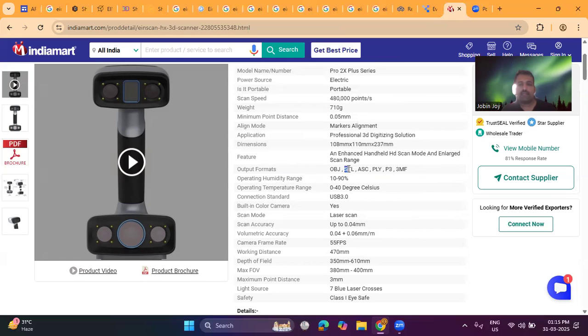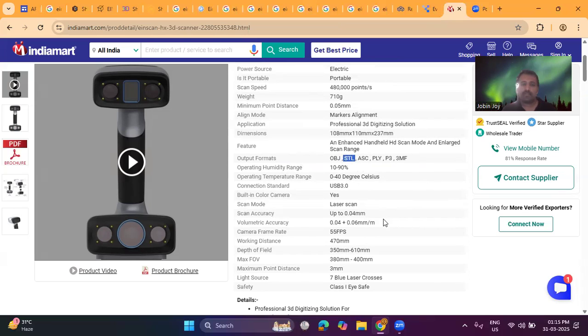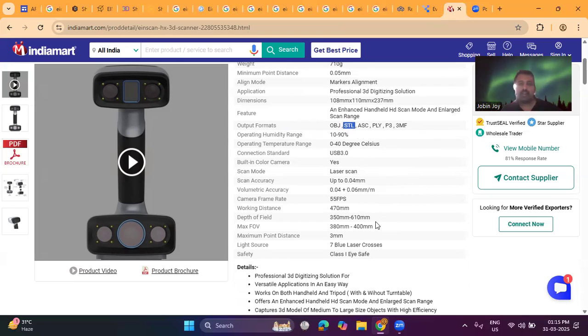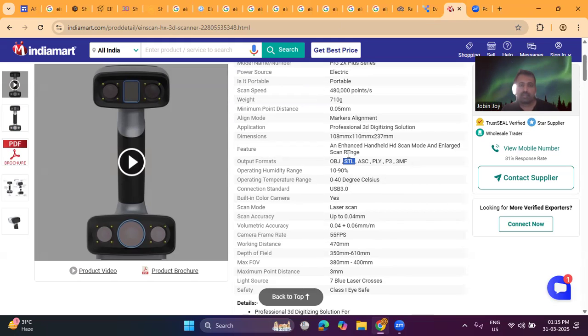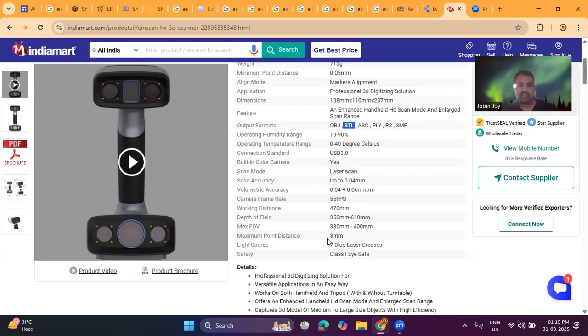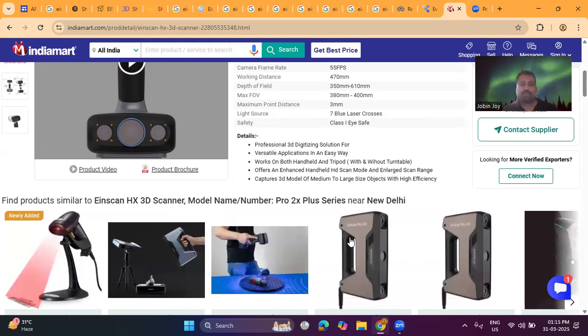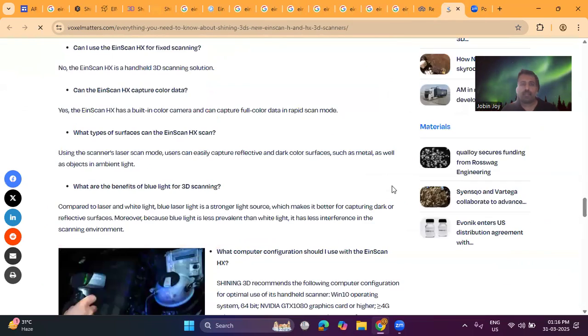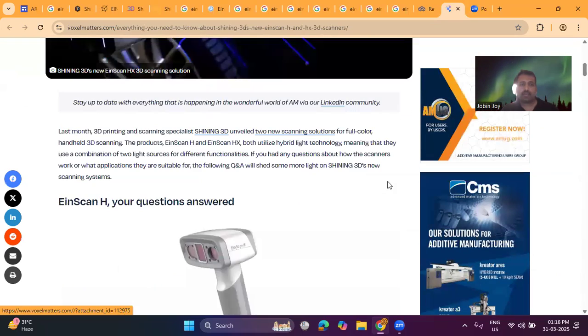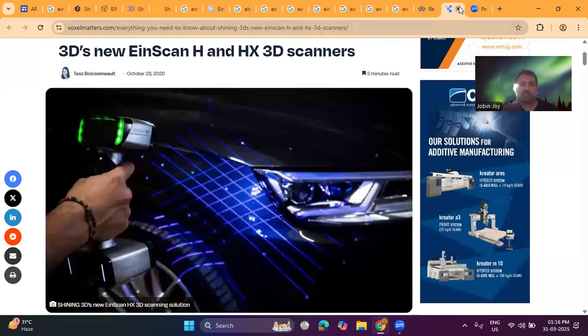For example, if you want to print your file, you have to convert the scanned file into STL format. The operating temperature range is 0 to 40 degrees Celsius. Connection is USB. There is a built-in color camera, the scan mode is laser, and the accuracy is up to 0.04 millimeter. The working distance is 470 millimeter. The minimum point distance is 0.05 millimeter, and the maximum point distance is 3 millimeter. This is another image showing some of the details about the scanner.